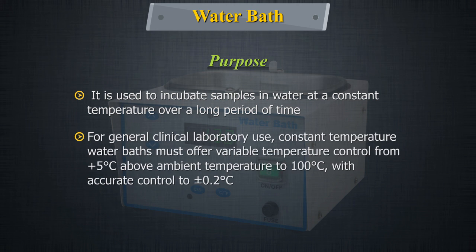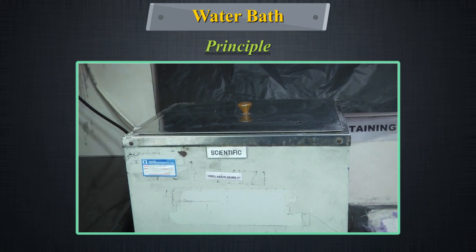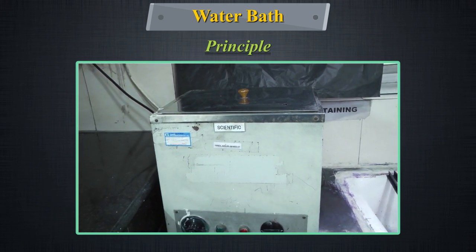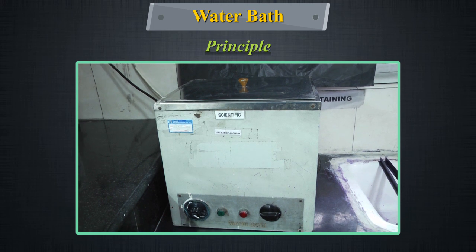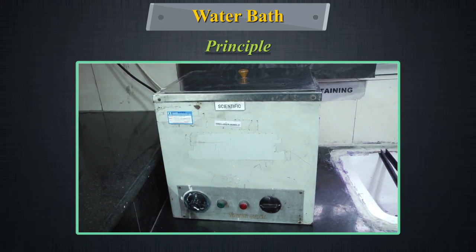For general clinical laboratory use, constant temperature water baths must offer variable temperature control from 5°C to 100°C with accurate control to ±0.2°C. Water baths are made of steel and are generally covered with electrostatic paint with high adherence and resistance to environmental laboratory conditions. Water baths have an external panel on which the controls can be found.